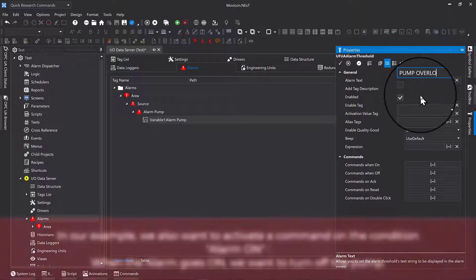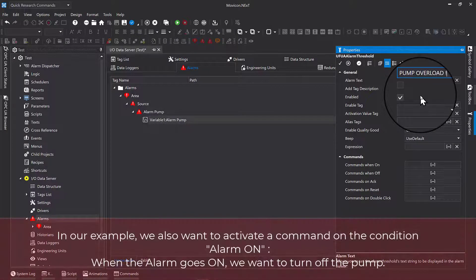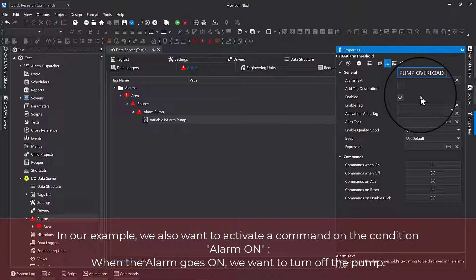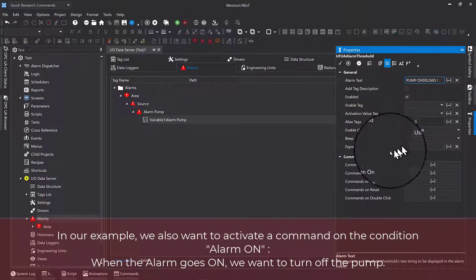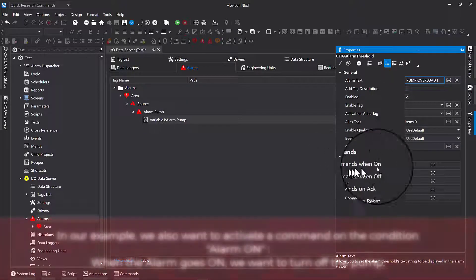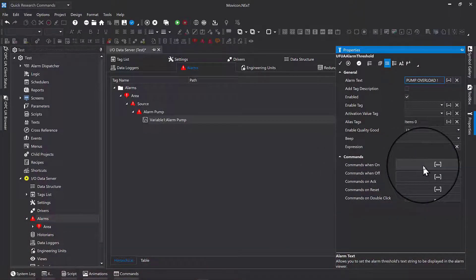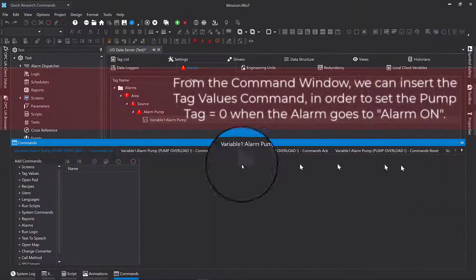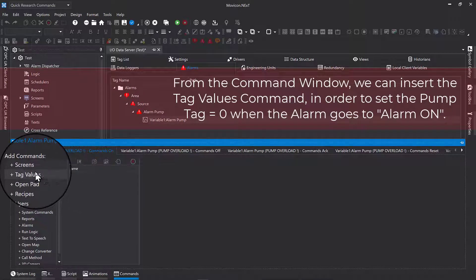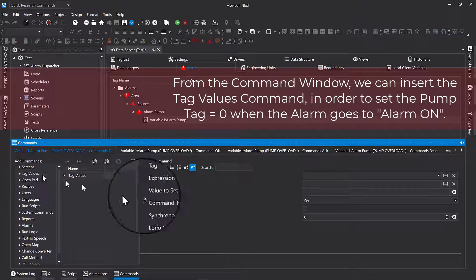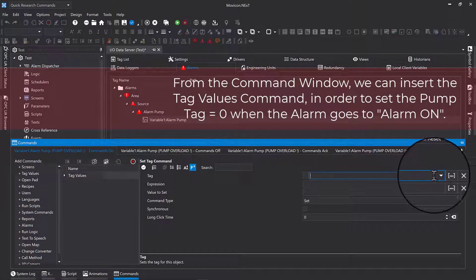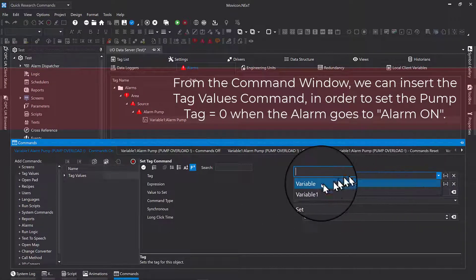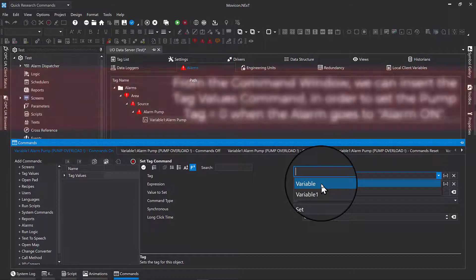In our example, we also want to activate a command on the condition alarm on. When the alarm goes on, we want to turn off the pump. From the command window, we can insert the tag values command in order to set the pump tag equals zero when the alarm goes to alarm on.